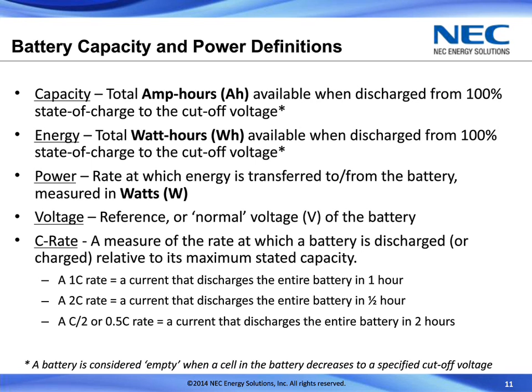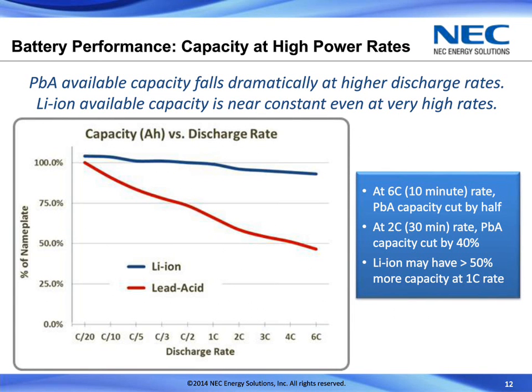So let's look at the first criteria for evaluation, which would be for battery performance, which would be capacity. And the thing to look at here is how capacity varies with the power level, or the power rate, at which we're using the battery. And this may not be something that everyone understands completely. It turns out it's a well-known attribute of most batteries, in particular lead-acid batteries, that as you take energy out of the battery at a higher rate, at higher powers, the actual capacity that's in that battery decreases. It actually decreases at a fairly rapid rate. Most lead-acid batteries are rated, when you say you have a 50 or 100 amp hour battery, at a 20-hour discharge rate, meaning that the current being pulled from that battery will take all the energy out of that battery in 20 hours.